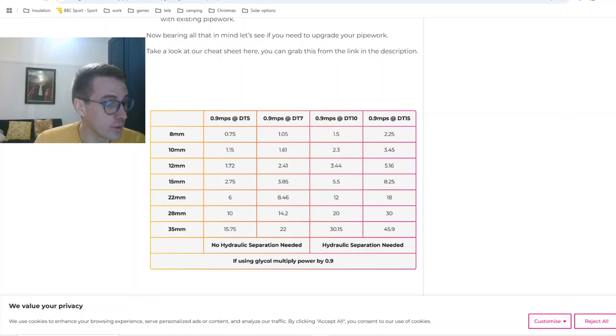So if we're only going upstairs and that only has a 2 kilowatt heat loss, if they're 15s, that's probably fine. And so we shouldn't have too much worry about that. So wonderful, that's great. That's that explained.